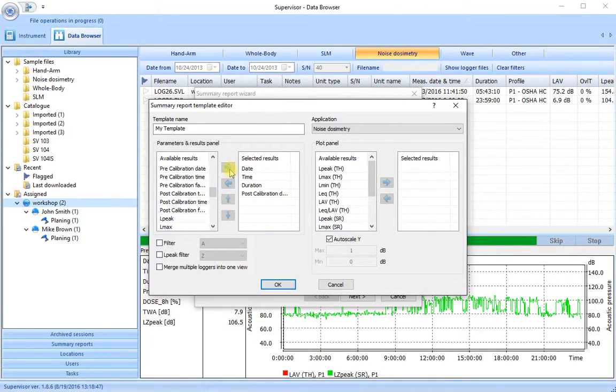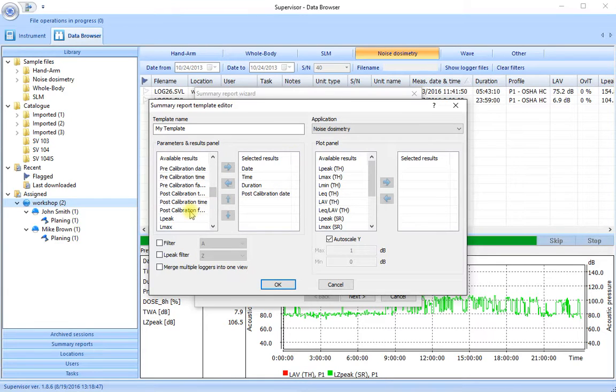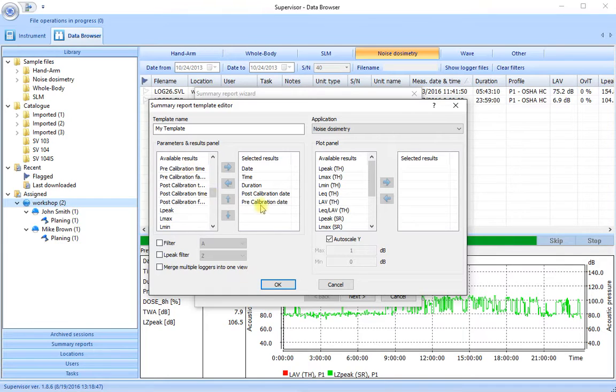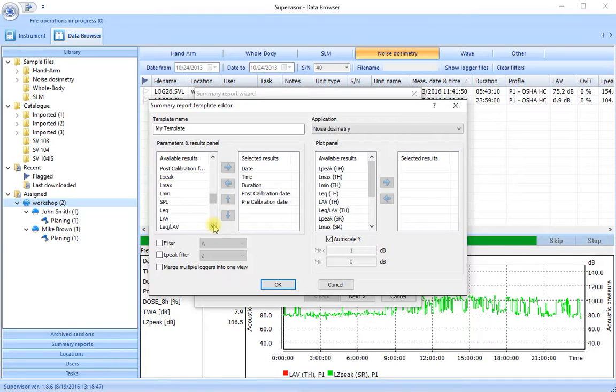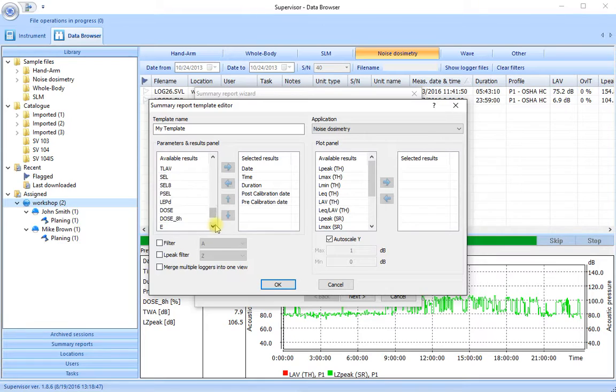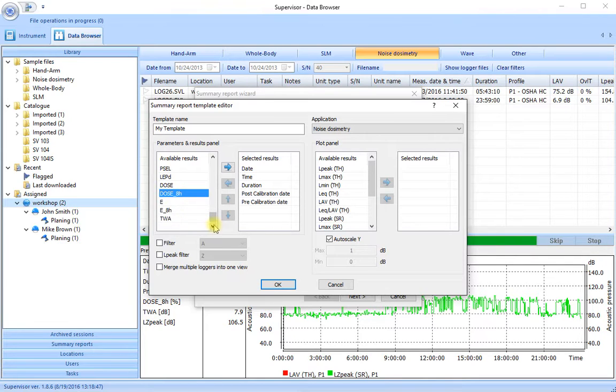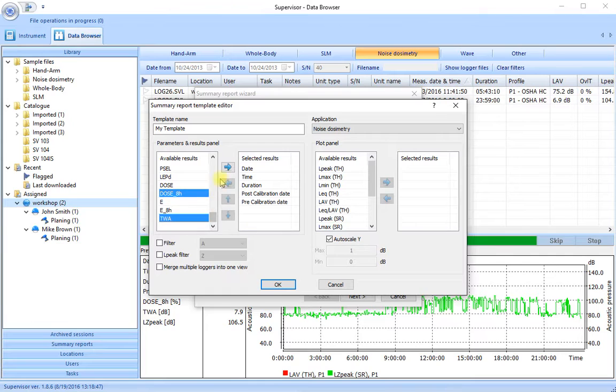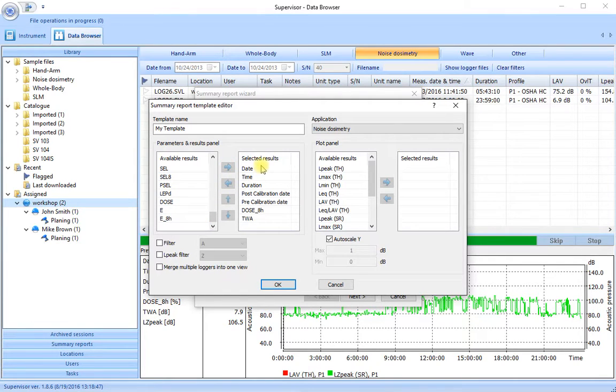We'll put in the calibration date. We'll have the pre-calibration date. So we have a record of doing the calibrations. We want a little bit of information here as well that will be useful. The projected eight hour dose and the time weighted average. So let's select those. Use the control key to select two of them. And then add those to the selected results here. So this is the text information.